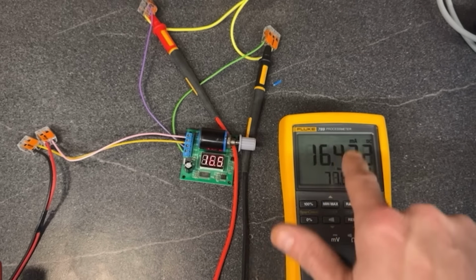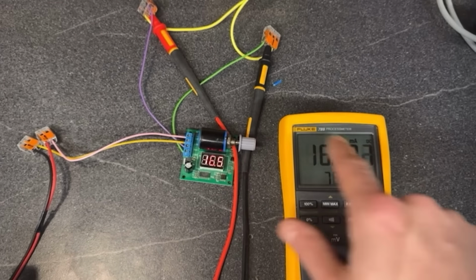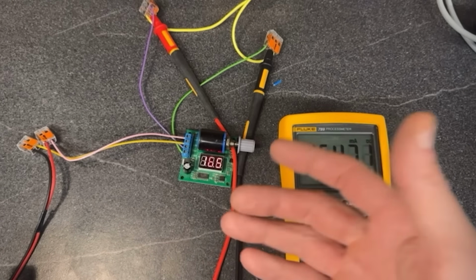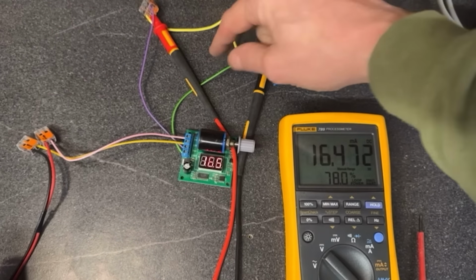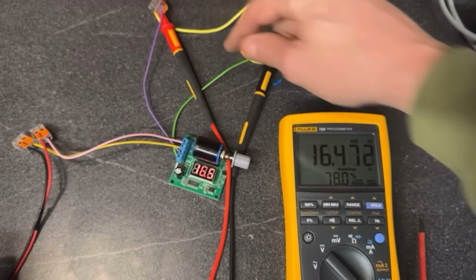However, the PLC hasn't got a screen, or it's got a SCADA or something, yeah? So I don't actually know what's going on at the terminals, and I don't know what to rely on. The question is: if I find this cable in the panel, how can I find out if there's 16 milliamps in there?